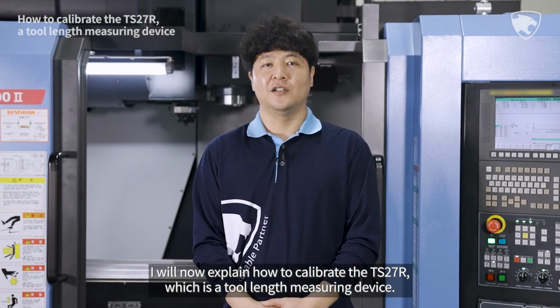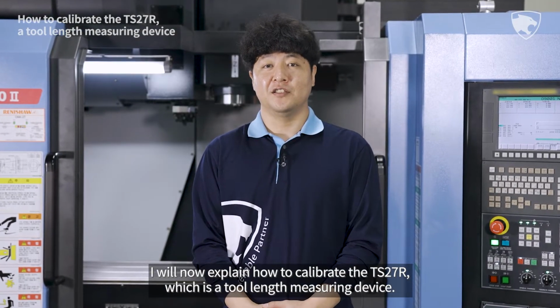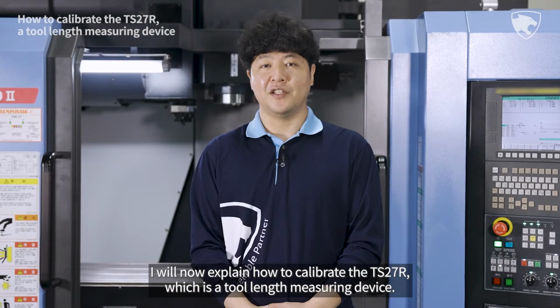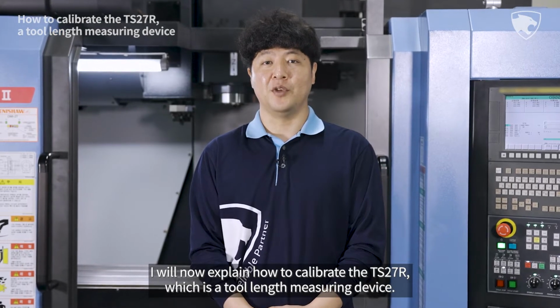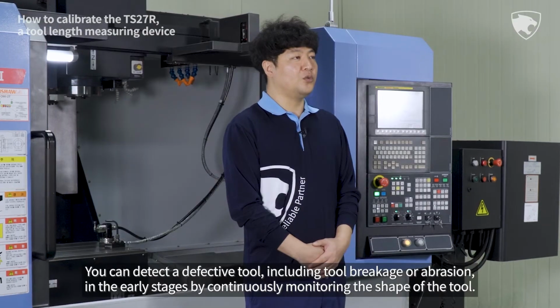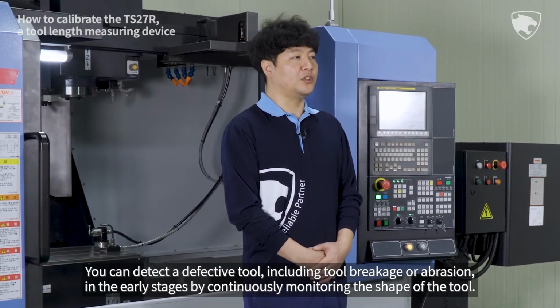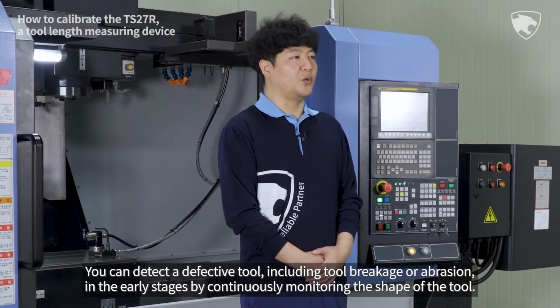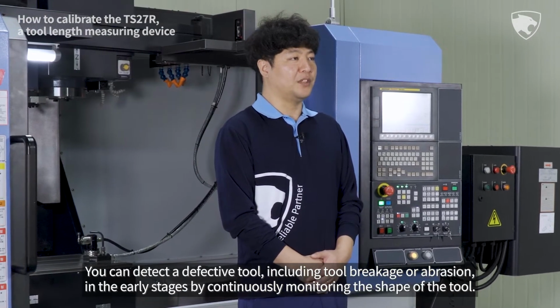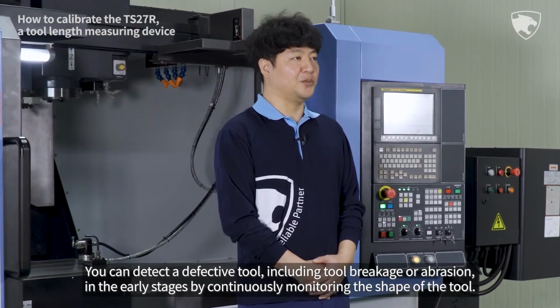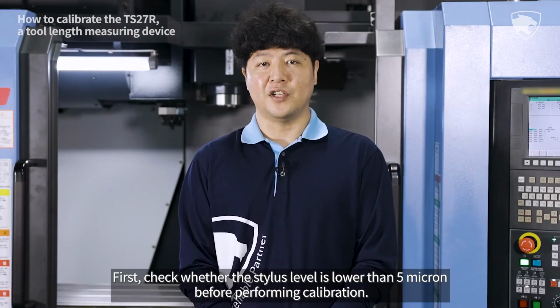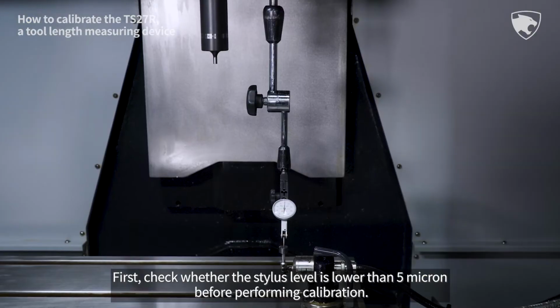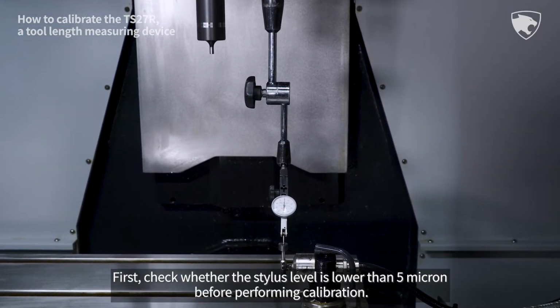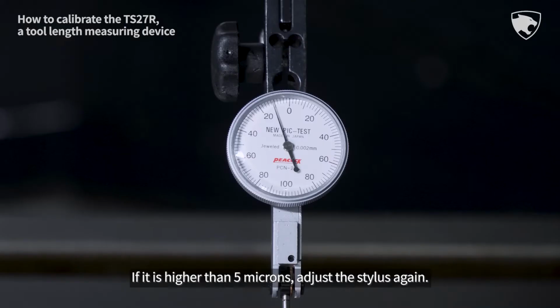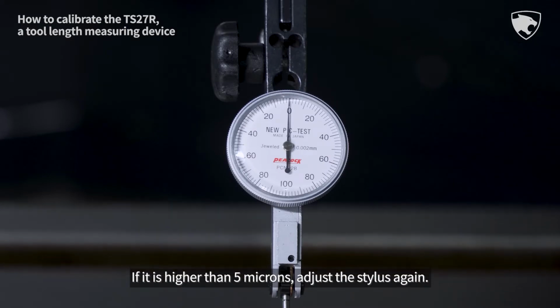I will now explain how to calibrate the TS27R, which is a tool length measuring device. You can detect a defective tool, including tool breakage or abrasion, in the early stages by continuously monitoring the shape of the tool. First, check whether the stylus level is lower than 5 microns before performing calibration. If it is higher than 5 microns, adjust the stylus again.